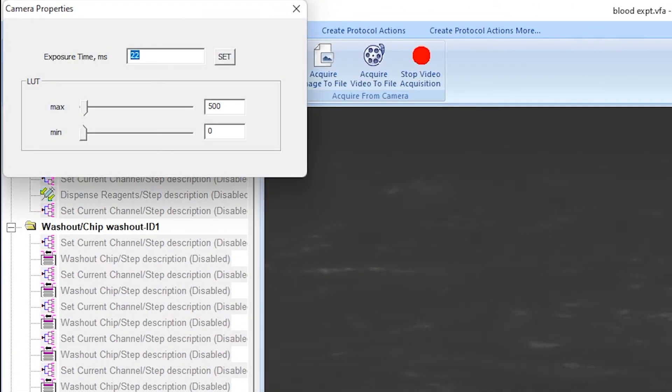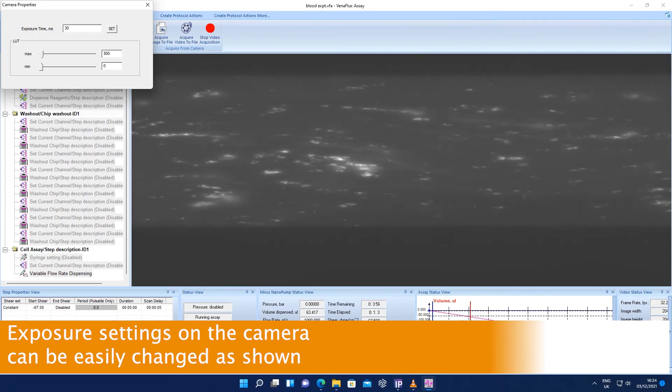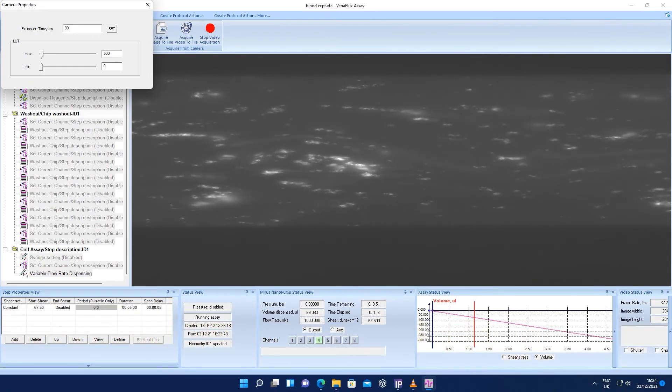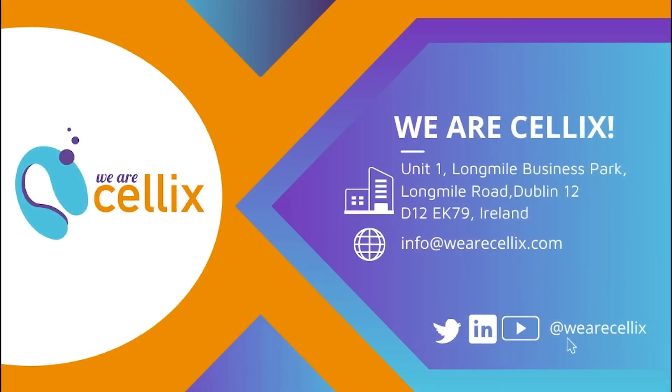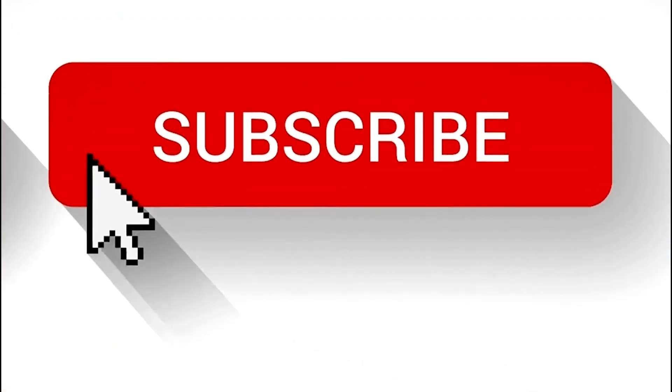Here you will see the volume of blood dispensed, the assay time elapsed, and assay time remaining. One advantage of the Venaflux Pro platform is the integration of the digital camera with the Venaflux assay software, meaning you can control the camera's exposure settings directly from the software as shown. And that's it — you've just completed your first thrombosis assay with Cellix's Venaflux Starter or Pro platforms. If you'd like to learn more about Venaflux solutions, check out the other videos on our channel or get in contact with us.